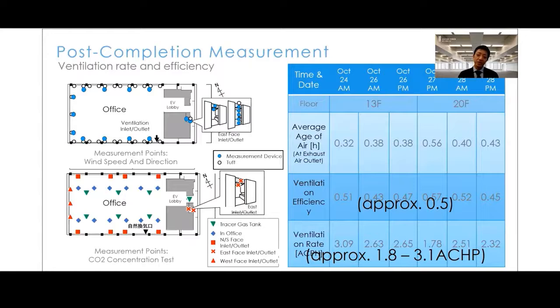The effect of natural ventilation was not only estimated during the design, but post-completion measurement was also conducted with the support of Professor Kurabuchi from Tokyo University of Science. As you may imagine, verification for such a dynamic system is not straightforward. Measurements, mainly of pressure, air velocity, air movement, and tracer gas density, were conducted during October 2019. The ventilation rate was measured ranging from 1.8 to 3.1 air changes per hour, with an efficiency of approximately 0.5.